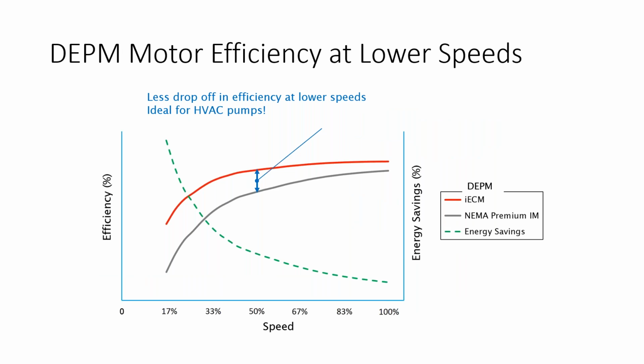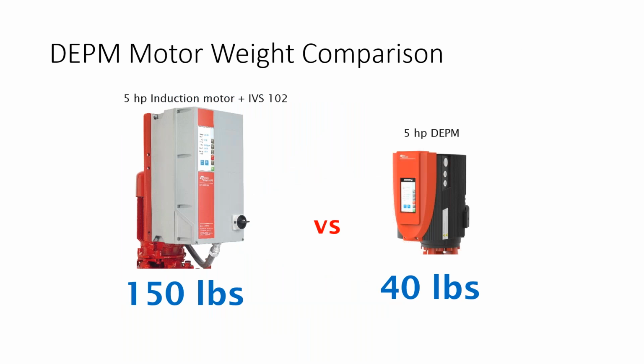So the efficiency is really where it matters here, because you saw that 2 to 13% efficiency. As the speed drops off, there's actually a higher efficiency between the ECM type motor and a NEMA Premium. You can see the efficiency right there. And as the speed drops, you'll see the efficiency drop on all designs of motors, but you actually get a higher output on the ECM motor, the permanent magnet motor, than you would on a NEMA Premium at lower speeds. Weight, oh wow, here's a big difference. A 5 horsepower induction motor with a controller built in, 150 pounds for a 5 horsepower motor, versus a 40-pound total design on the motor and controller with permanent magnet motors. So right there, somebody's back just got saved.